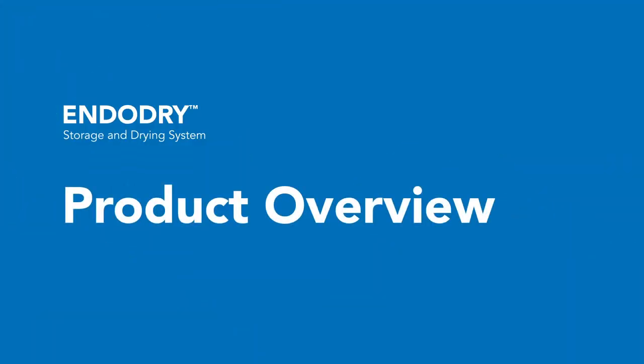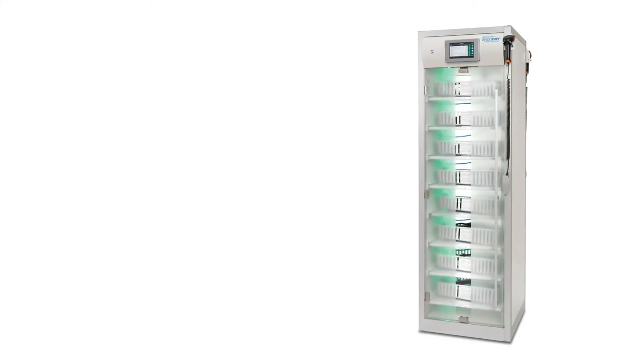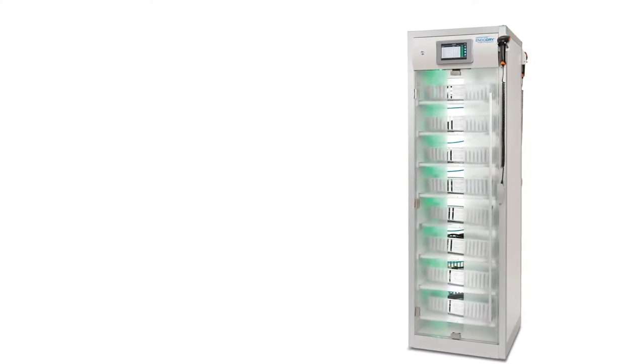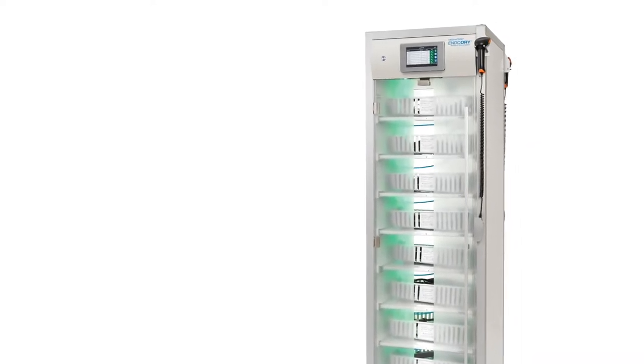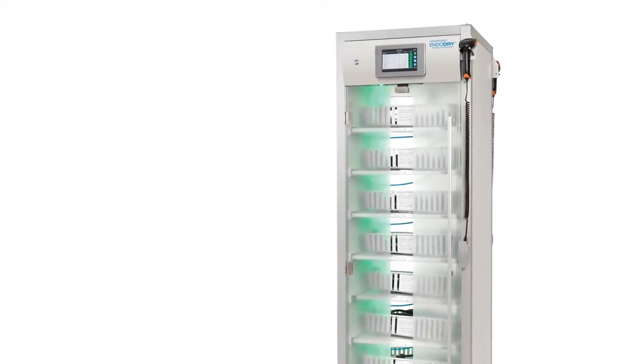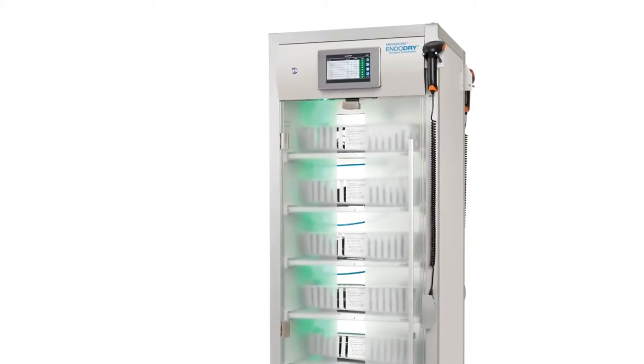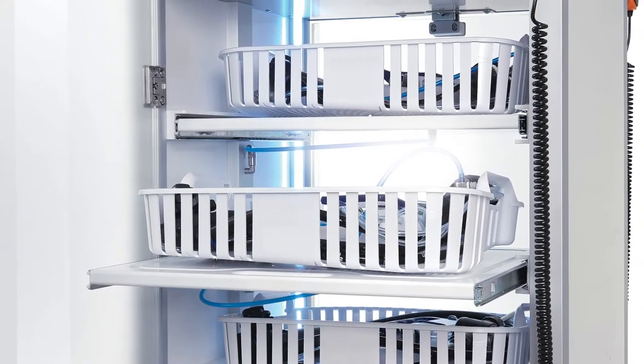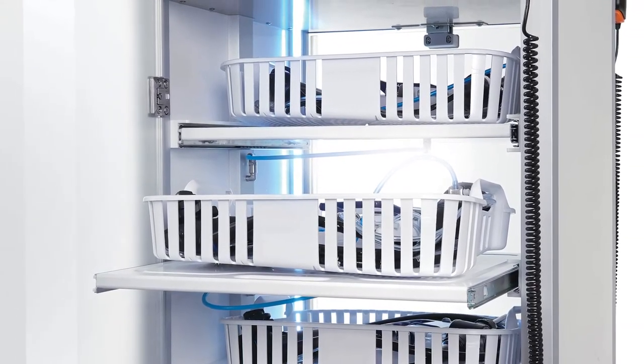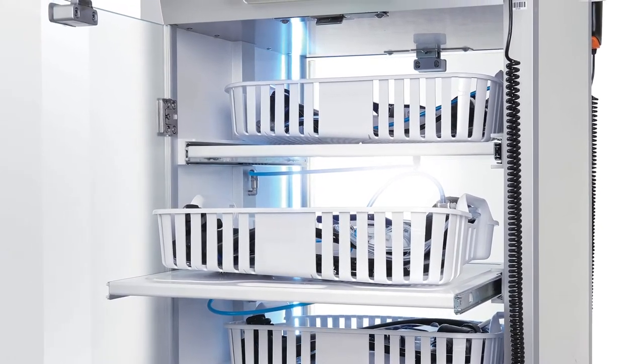The EndoDry Storage and Drying System is a cabinet used to dry and store up to eight endoscopes horizontally. It uses compressed filtered air that is continuously circulated throughout the endoscope channels and cabinet. Instrument air is recommended. The EndoDry cabinet is compatible with many manufacturers' flexible endoscopes, including Olympus, Pentax, Fujifilm, and Karl Storz endoscopes.